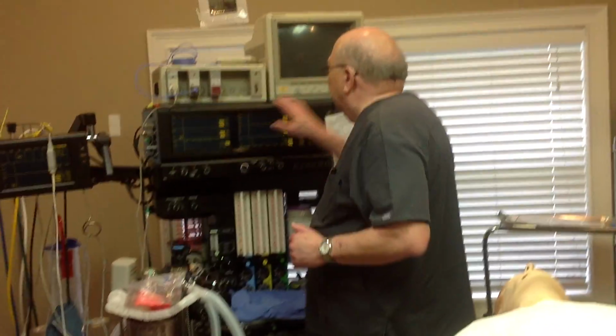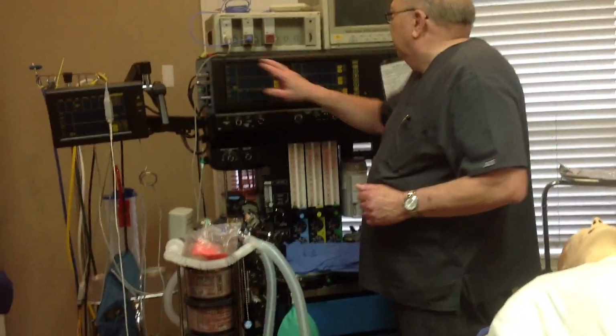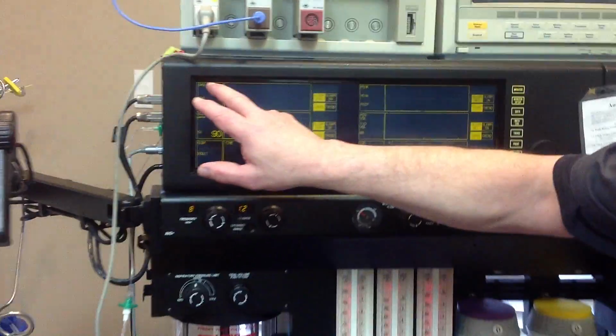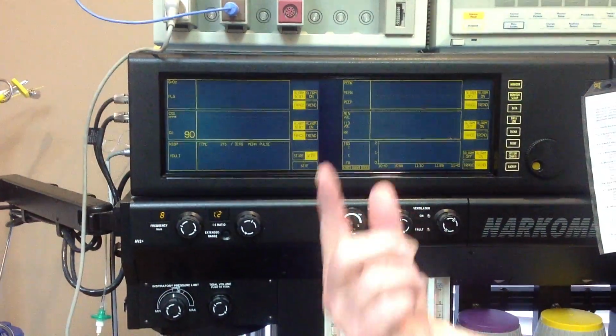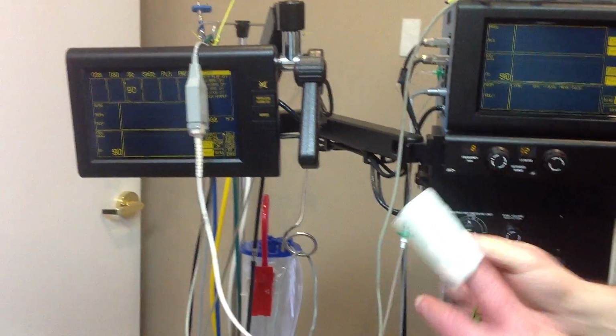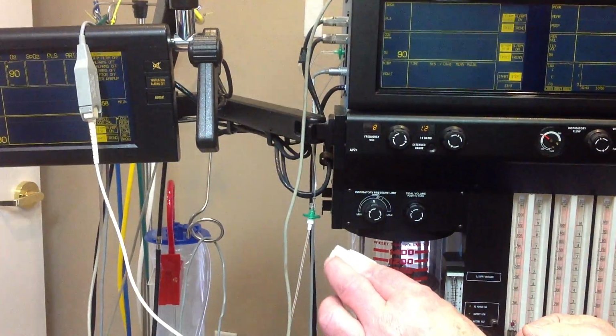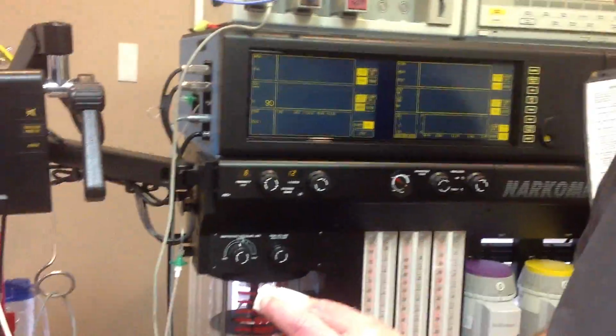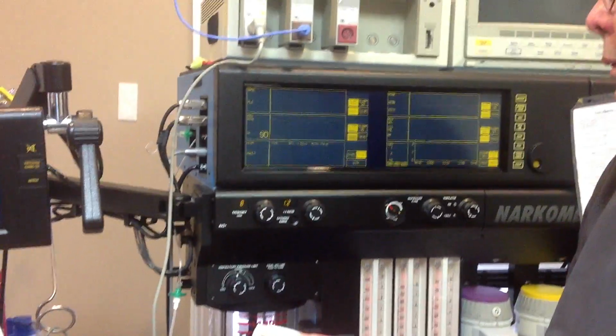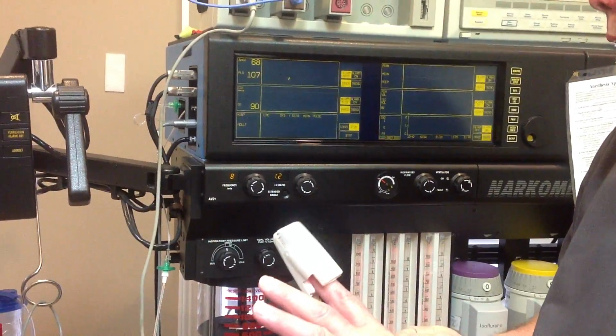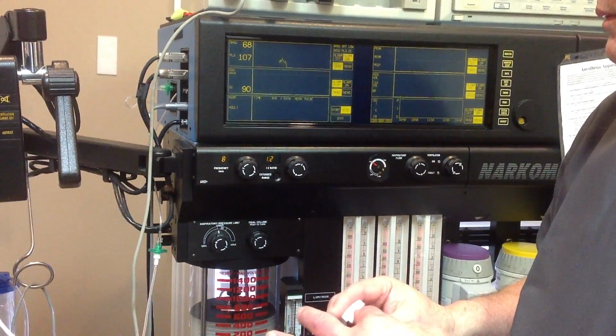Okay, let's go back to the beginning. All right, this is the first screen of this machine, and it's called the monitor screen. That's all your monitors. So your first one up here is your SaO2, then your pulse off of your pulse oximeter over here. So if I put that on, I will start getting it. You'll start reading it. It's working. There it goes. So I'm high.